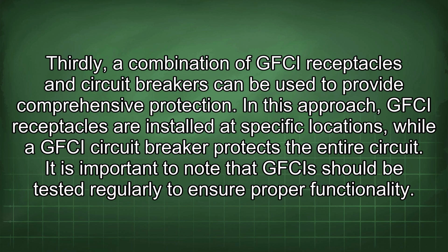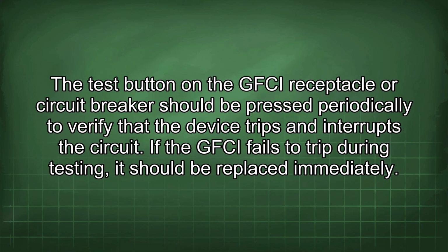It is important to note that GFCIs should be tested regularly to ensure proper functionality. The test button on a GFCI receptacle or circuit breaker should be pressed periodically to verify that the device trips and interrupts the circuit. If the GFCI fails to trip during testing, it should be replaced immediately.